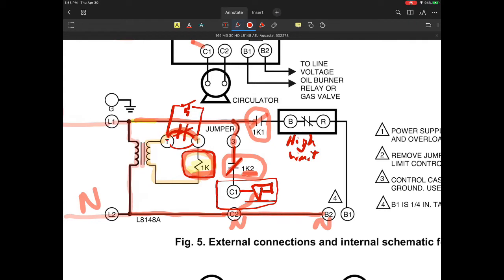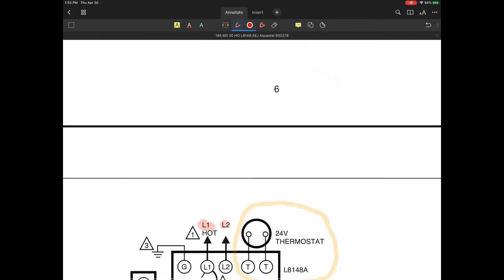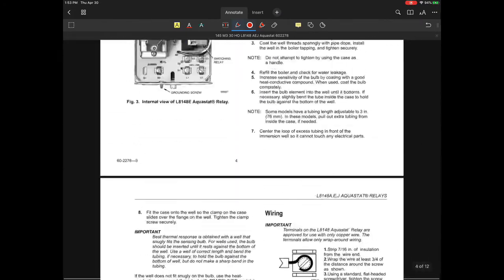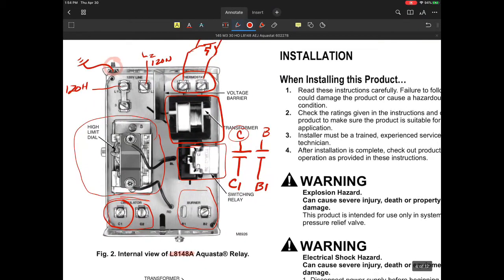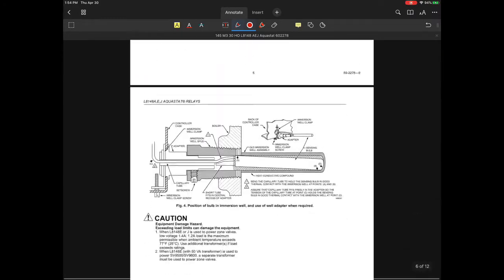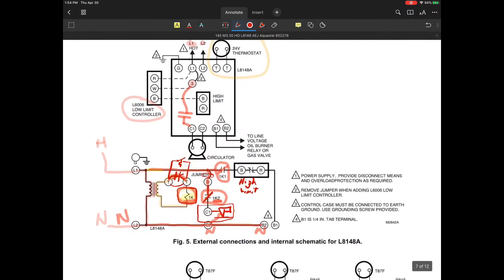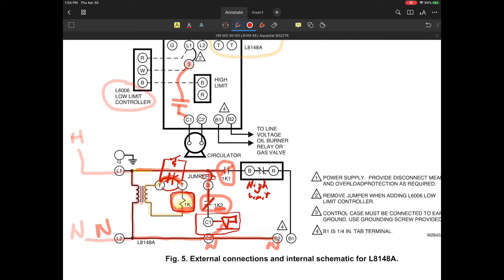The point I want to make here is that any time there is a heating demand, the way this is wired, that circulator will always be running. You can see how that's set. If there's a demand, this closes, and you power your circulator 100% of the time. The only way that would change is if you were to put a low limit type of device on that jumper. On your Aquastat, and I'm going to go back to the Aquastat device here, there was a jumper, and the jumper they're referring to is this one right there. That's the jumper that they are describing.